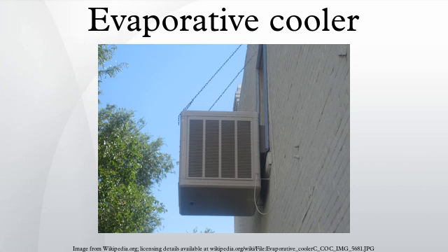The evaporative system cannot function without exhausting the continuous supply of cooled air to the outside. Depending on the placement of a single cooled air inlet, along with the layout of the house passages, related doors and room windows, the system can be used most effectively to direct the cooled air to the required areas. A well-designed layout can very effectively scavenge and expel the hot air from desired areas without the need for an above-ceiling ducted venting system. Continuous airflow is essential, so the exhaust windows or vents must not restrict the volume and passage of air being introduced by the evaporative cooling machine.